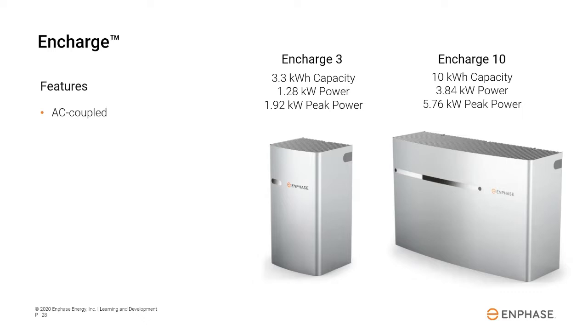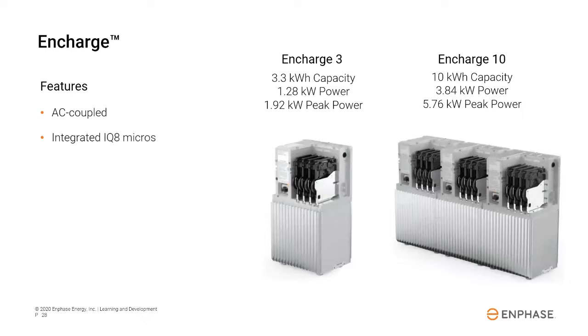The Enphase storage system is an AC coupled energy storage system, meaning that there is DC to AC conversion both at the solar array and at the battery system. Each Encharge battery unit has multiple integrated IQ8 microinverters, which provide redundancy and improve the reliability of the system compared to other storage manufacturers that just have a single inverter.